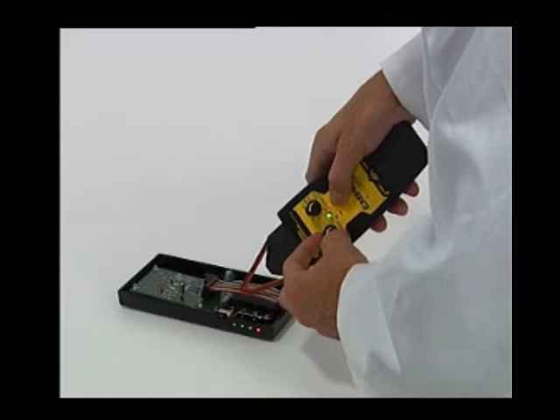To allow closer location of the area, we have now attached the smaller EMLocator probe. By using the short section and the tip of the probe, small areas can be accessed. By reducing the power control and sweeping closer to the ribbon, a single conductor in the ribbon cable can be identified.